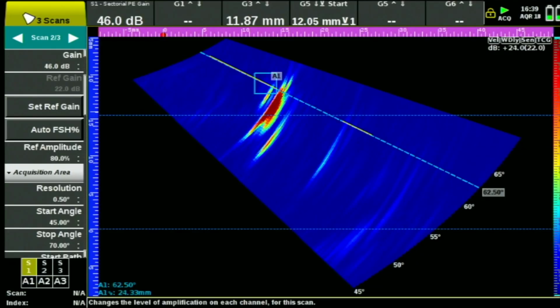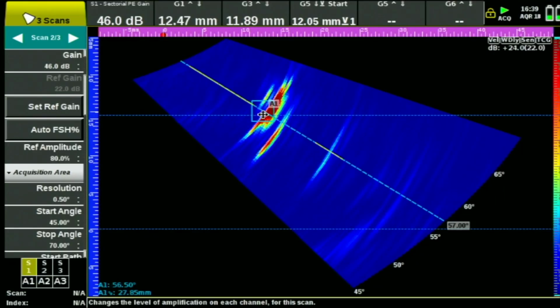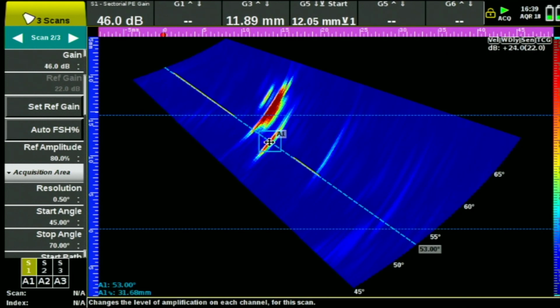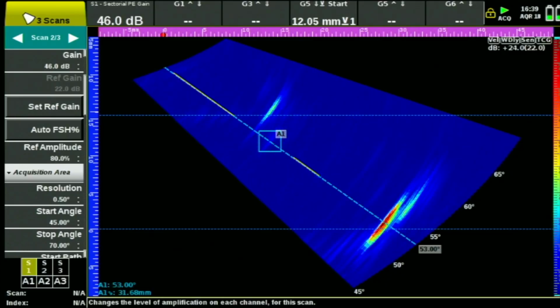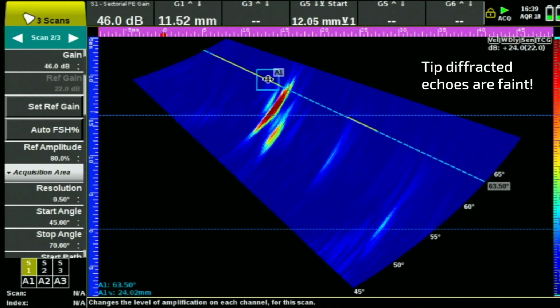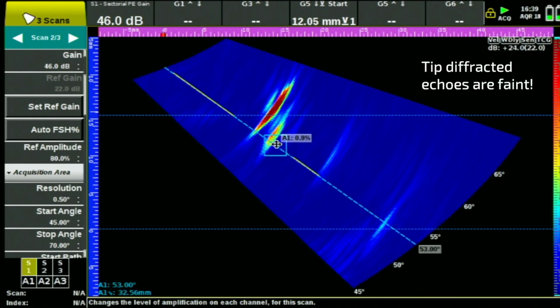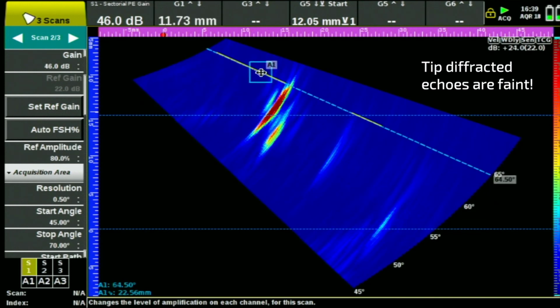So as we move the probe back and forth, we can see that we have a large reflector down here. Now that's amplitude is so high, it's probably a reflected signal. Now that's in the second leg, so what's happening is the sound is going down like this, back and up again. That probably indicates the crack has a little bit of a hook on the top. And if we look on the first leg signal, I don't see a whole lot up there. Maybe this one. And we have to sort of gauge which one of these is furthest from the back wall.